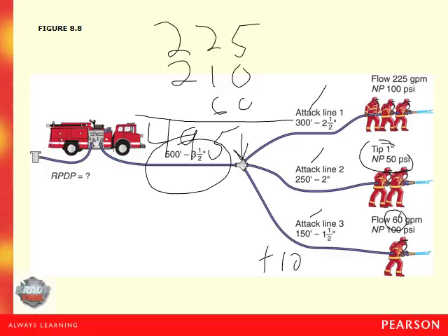So now we do our friction loss equal our coefficient, which is 0.34. Again, we get that off the chart. Don't forget the decimal. Multiply that by our gallons per minute. So that's 495 divided by 100, which is 4.95. You know, we just have to move the decimal place over twice. And then 500 divided by 100 is 5.